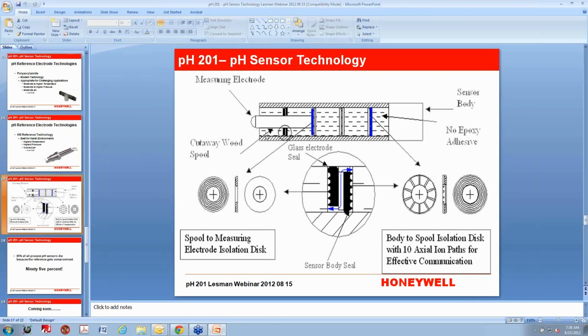The front one is a piece of Teflon, and then you have 5 wood sections, and in between these wood sections there are wooden dowels that have a hole drilled in the middle for the glass stem to come through. And in between each of these wooden dowels is a set of Viton seals. These seals are sized such that one seal seals up against the glass, but not against the body, and the other one doesn't seal against the glass, but it does seal against the body.